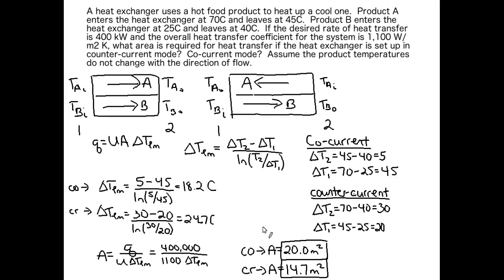We can also figure out, well, what should the overall heat transfer coefficient of our system be? That can tell you things like when is it time to clean the heat exchanger because our overall heat transfer coefficient has dropped too low due to fouling or some other kind of issue that blocks heat transfer. So you can figure out a maintenance schedule from your heat exchanger design equation. There's tons of applications for this. Just remember that it does matter if you set up in co-current versus counter current mode, and you do need to bring together many different heat transfer principles to be able to solve the particular design question.